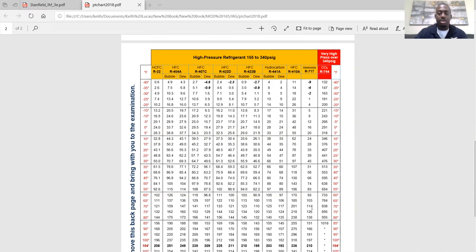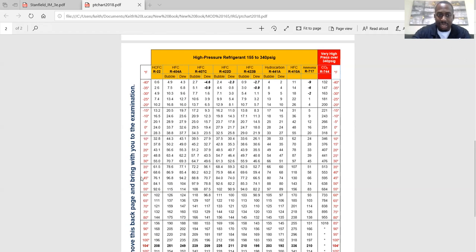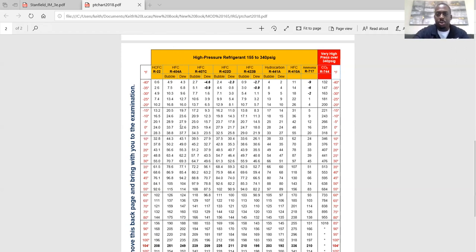Your superheat and subcool will be way off if you're looking at the wrong refrigerant number. If you have R22 in your system but you think it's 410A — you read 78 PSI and assume the saturation temperature is 20 degrees, but it's actually 45 — you're going to be confused because you're looking at the wrong refrigerant.